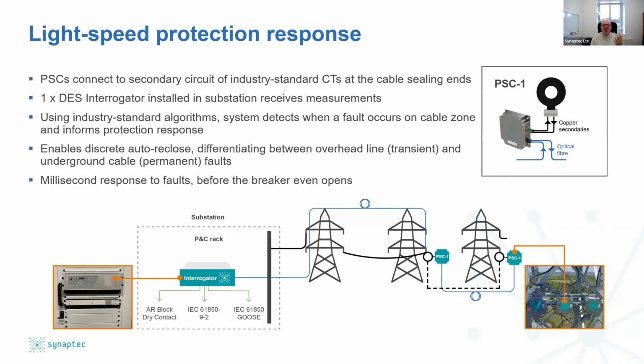What we're simply doing is signposting, or informing the protection scheme where the fault is if it occurs. And in fact, we've had an example recently where we helped an operator manage a fault correctly with the system installed, where you've got an overhead fault. We've said, good, if the fault's in the overhead section, you can reclose. If the fault's in the cable section, we'll tell it straight away, and we'll see it within milliseconds from the differential currents that are measured centrally. We can say, no, for sure, and in protection timescales, yes, that fault is in the cable section, so we're going to recommend that you block the auto reclose and don't reclose on that fault, right? So this has a significant cost saving and an outage saving.